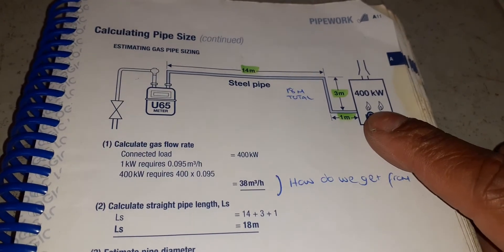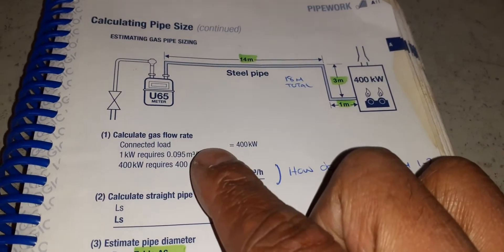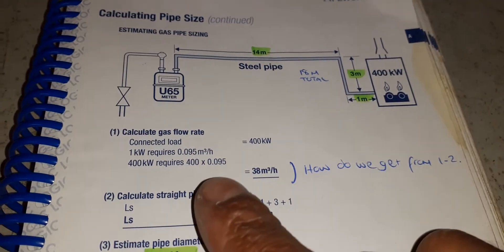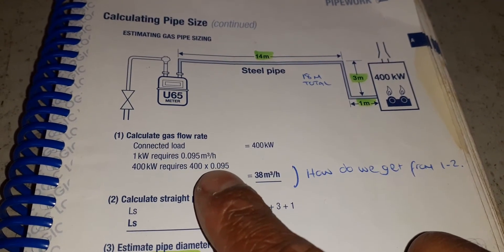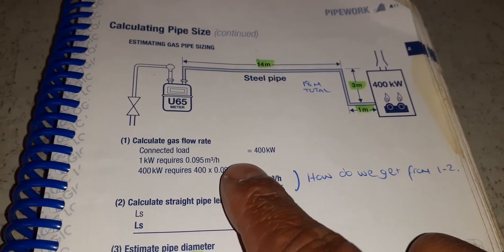As you can see in this book here, it says calculate gas flow rate. Connected load: one kilowatt requires 0.095 meters cubed an hour of gas.